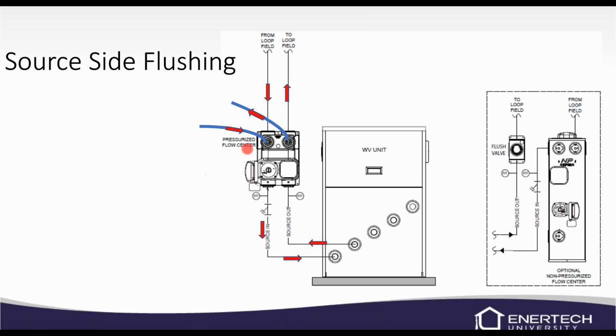Source side flushing, it's pretty easy. Obviously on a pressurized system, you're going to shut off your flush ports to the unit and you're going to flush out through the loop field. On a non-pressurized system, it's got PVC in it and we do not want to flush through it. So there is a little spot on the side of the non-pressurized flow center here that you can put a double O-ring fitting, but you will have to have a second flush block.